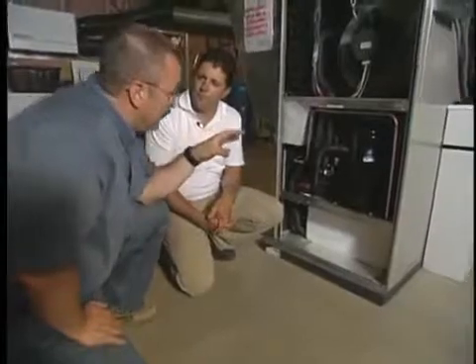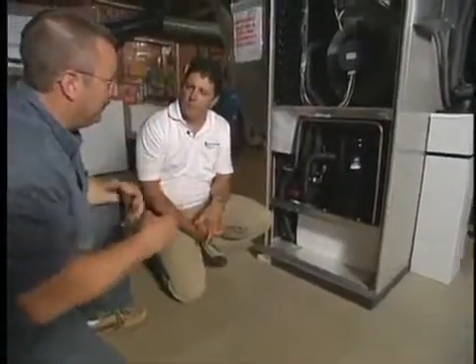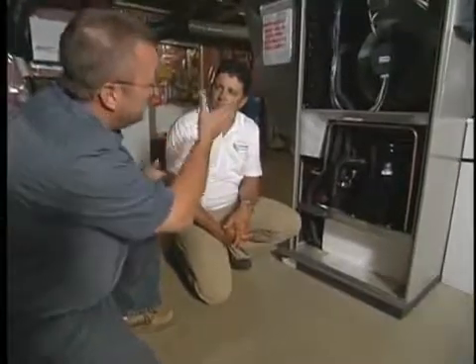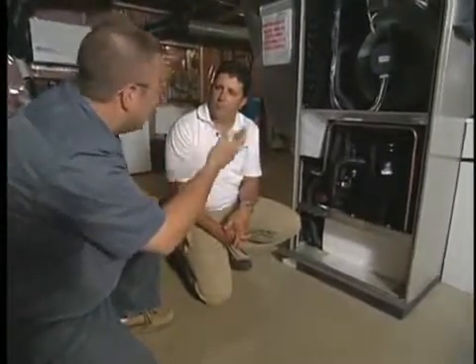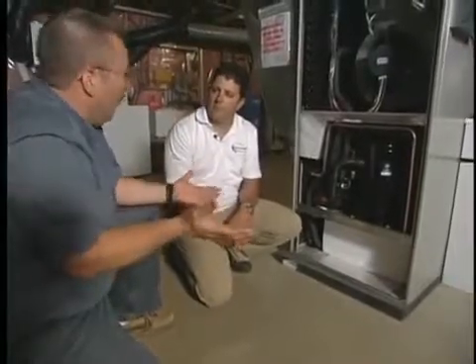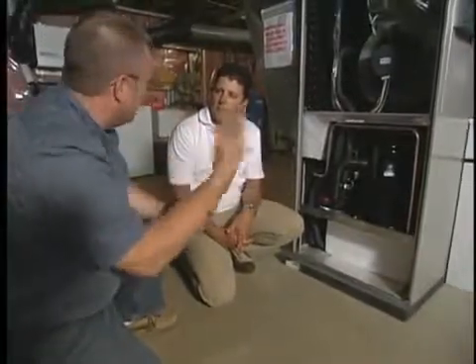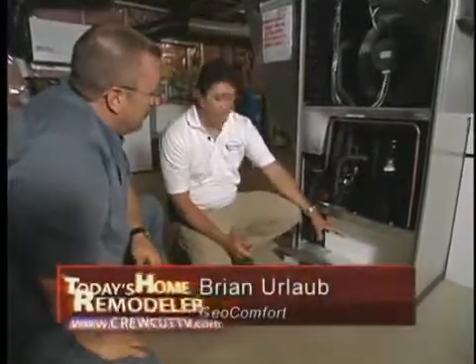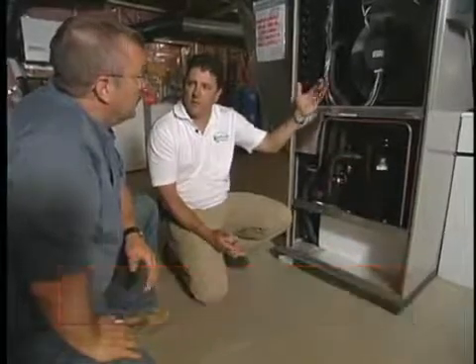So of course, when you use the term intensify, what that compressor is doing is raising the temperature of that refrigerant up to, say, about 100 degrees, 120 degrees, somewhere in there, so that then it can be distributed through the house, because you wouldn't want 50-degree air being circulated through during the wintertime. Yeah, that's exactly right, Stu. We've got 50-degree, 40-degree groundwater coming in. This is intensifying it to about 100 degrees, which then will keep your home nice and comfortable at 70, 72 degrees.